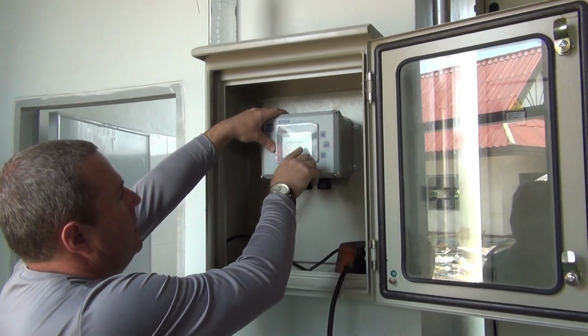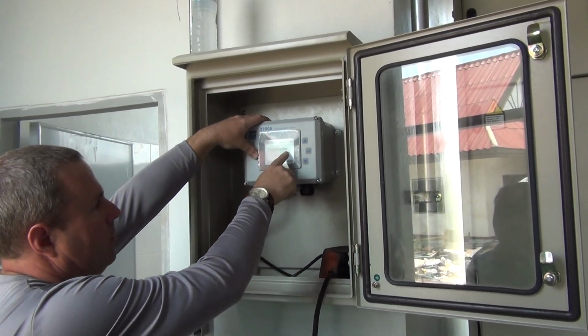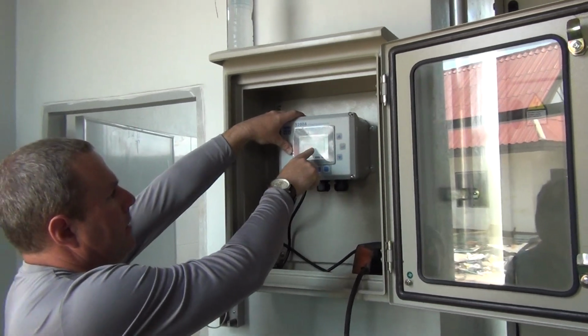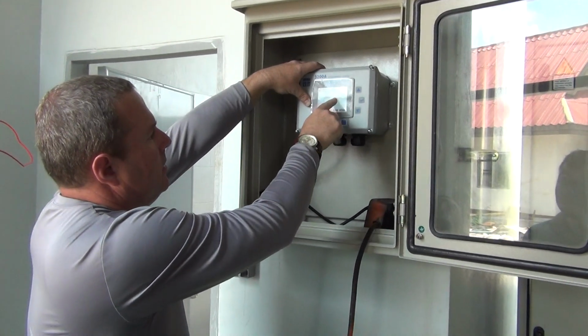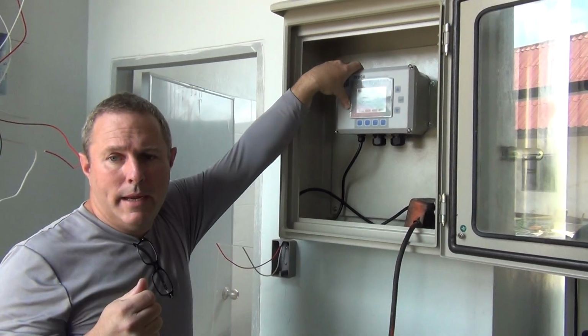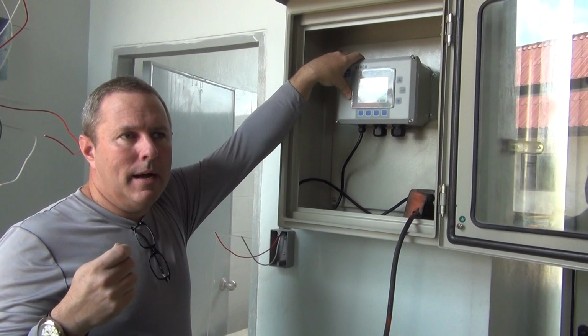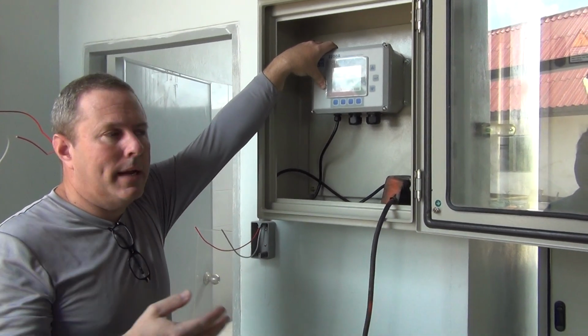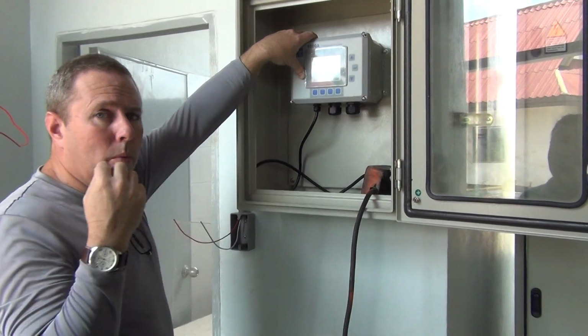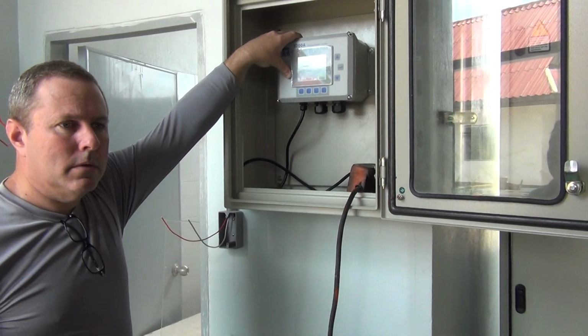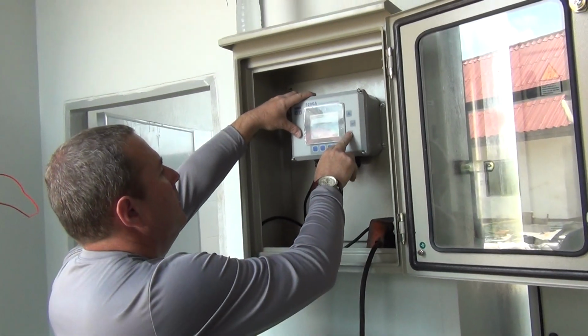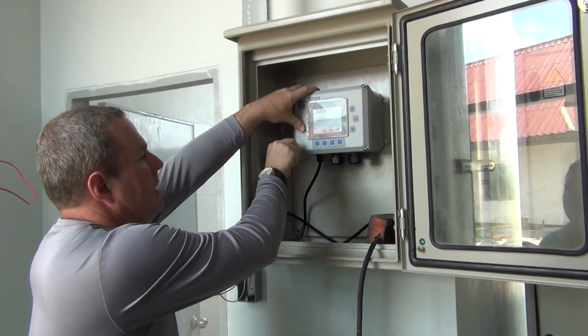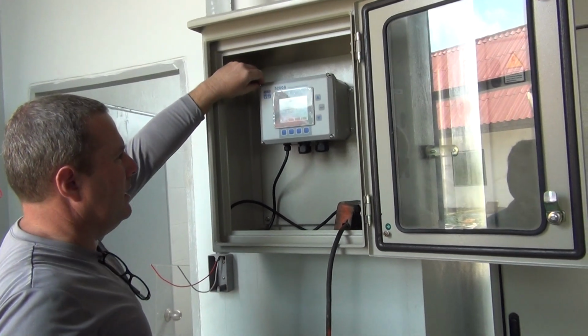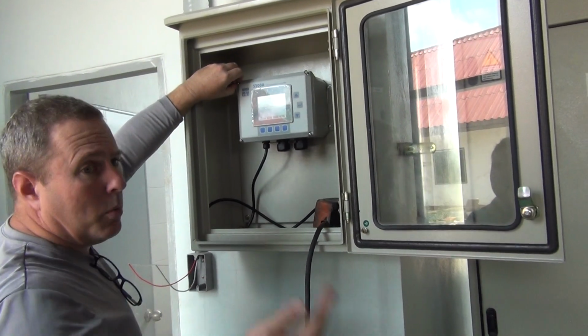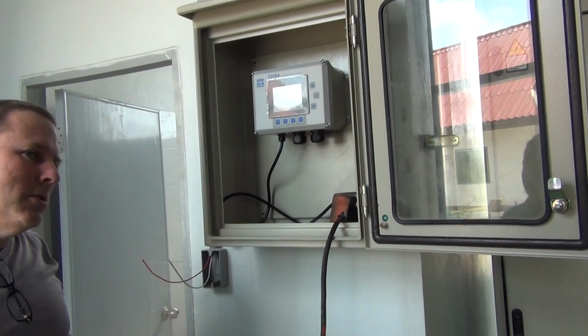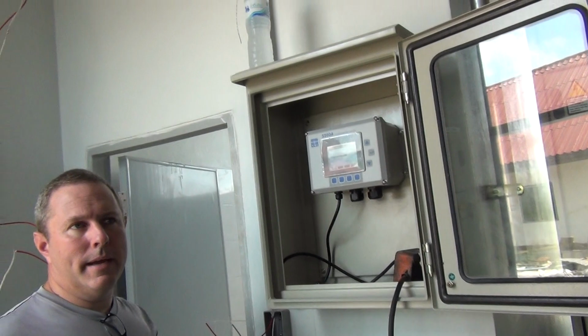Now, send test email message. We can choose how we send it. The option is through the Ethernet. So that's why we would need to have internet access to a PC and to the internet through the Ethernet so that we can send the messages to the telephones. Okay? So then, the next item, email time delay. If there's a situation that's going to set an alarm, do we want it to send the message right away? Or do we want to wait to see if the situation calms down? And then it can do a delay.